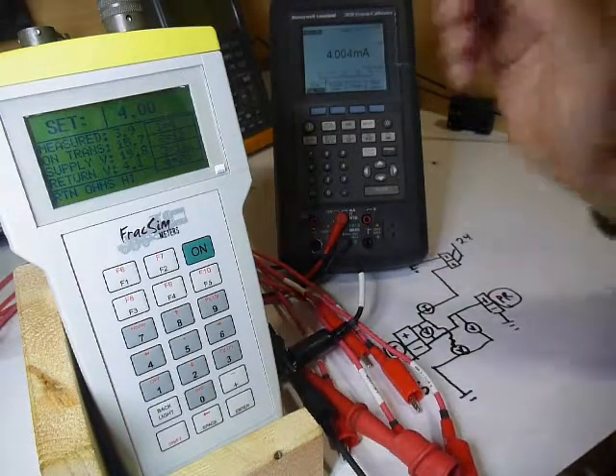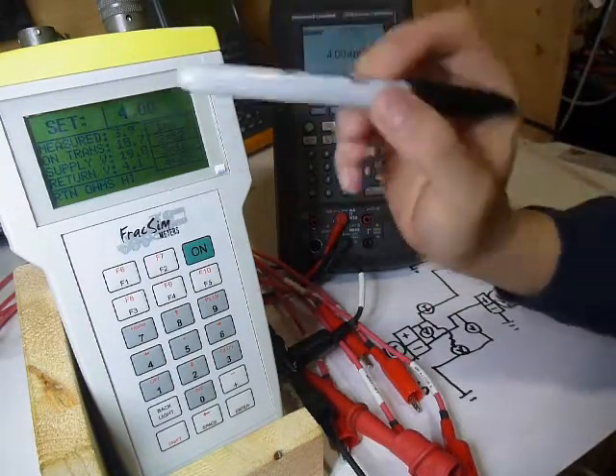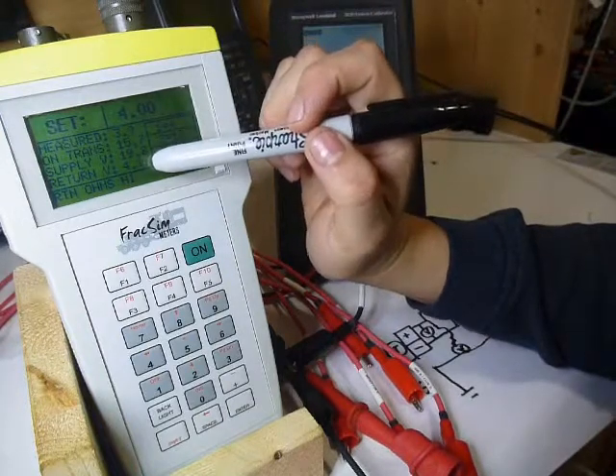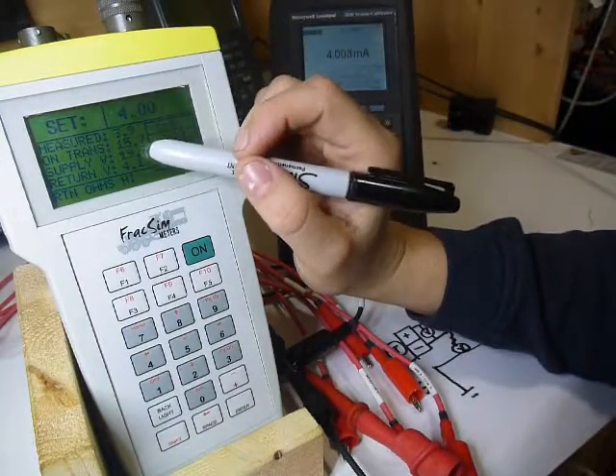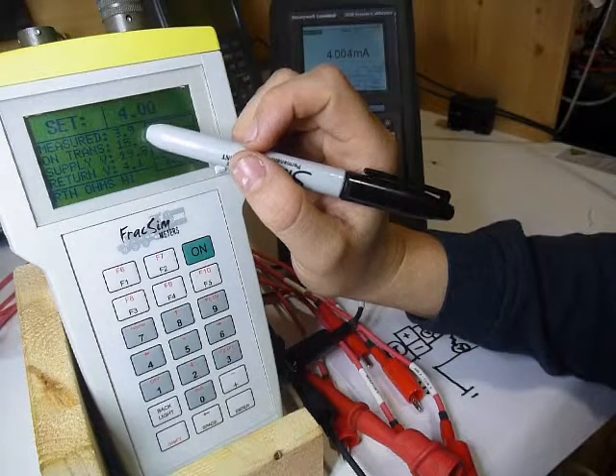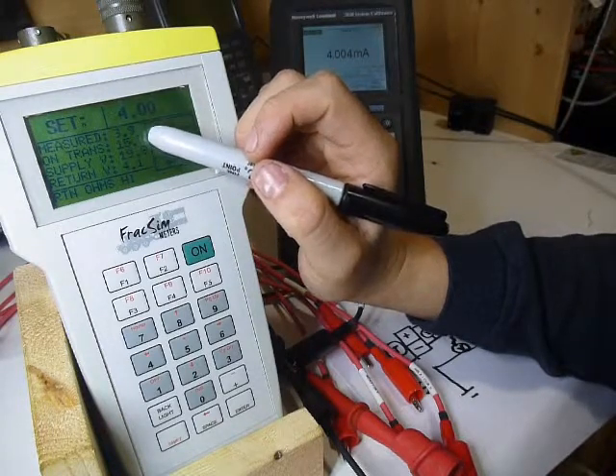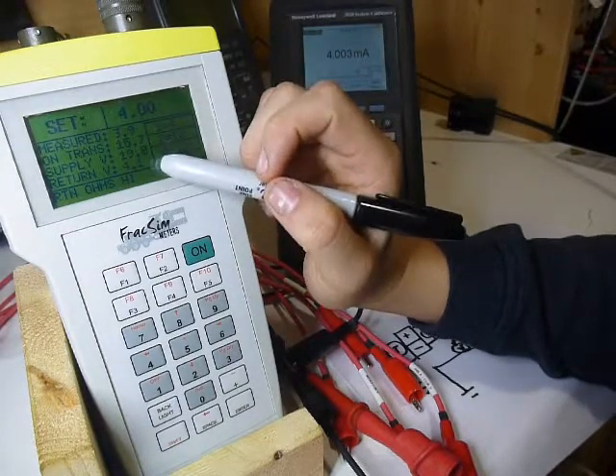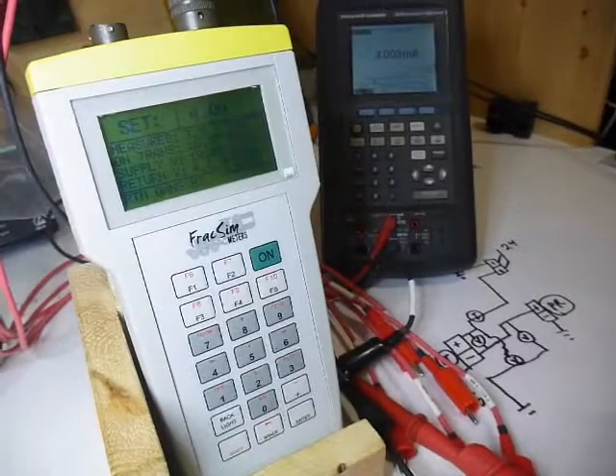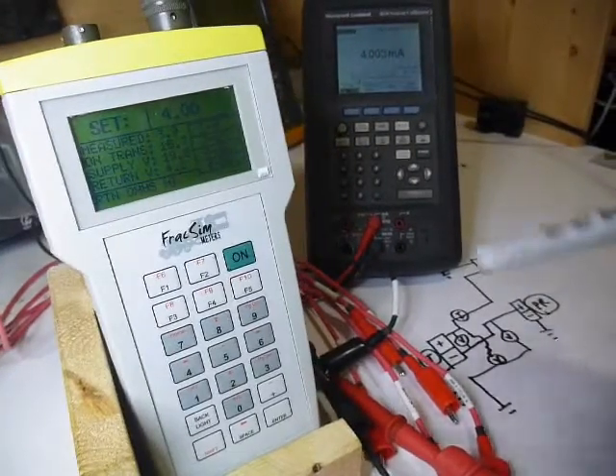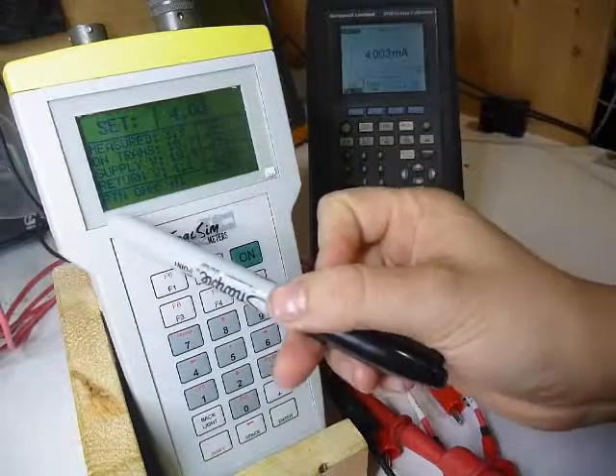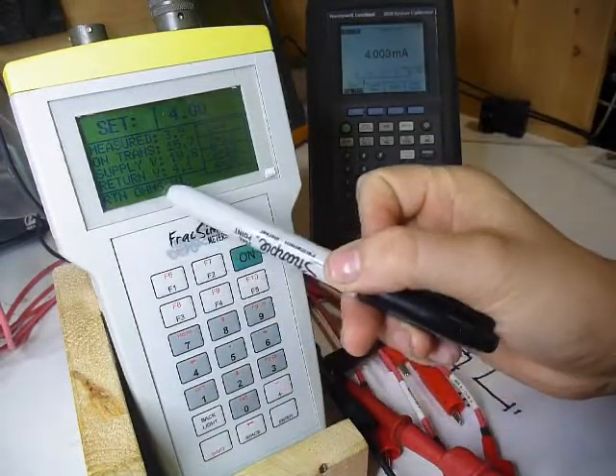So it's a 1k ohm resistor, 4 milliamps, so we should have a drop of 4 volts, which we do. So we're starting at 20, or just under 20, and we should be at just under 16. And that is correct, and that is due to that 1000 ohm resistance. And if you actually see at the bottom here, it's giving us a warning now. It says return ohms high.